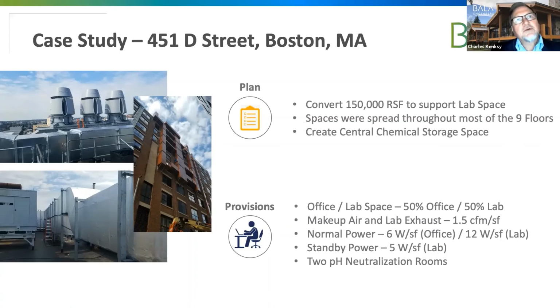If you look in the picture on the right, there's red ductwork coming down. Not every floor had labs, so we had to get the ductwork to the spaces that were going to become labs. This is an alley side, and they ran the ductwork down and painted it to match the brick. From an engineering standpoint we love that, but I know architects don't.